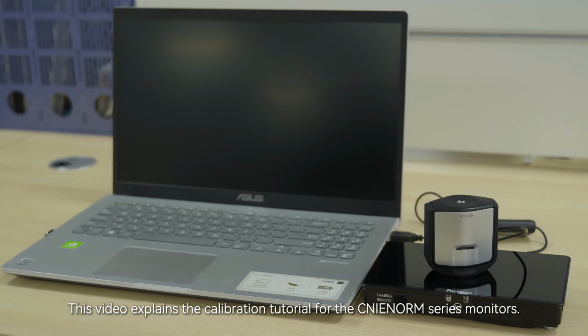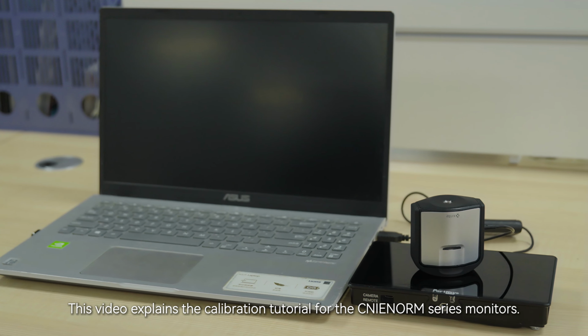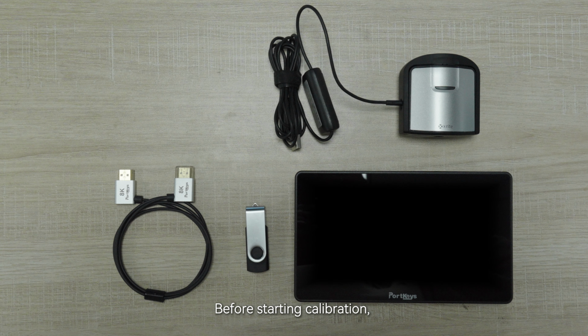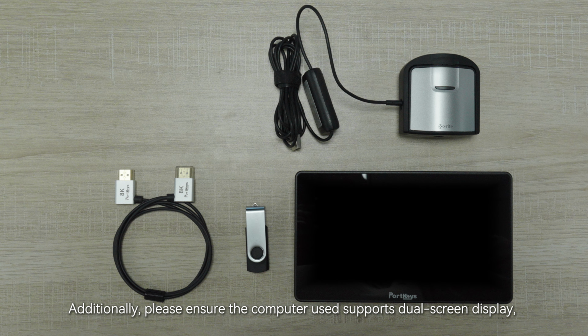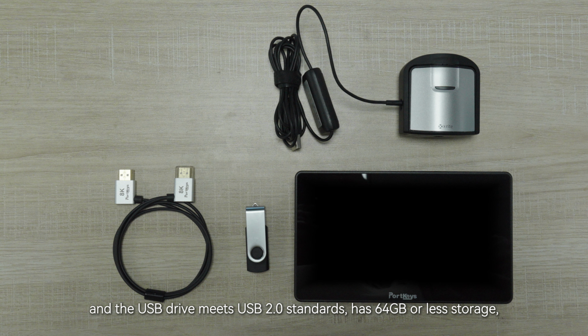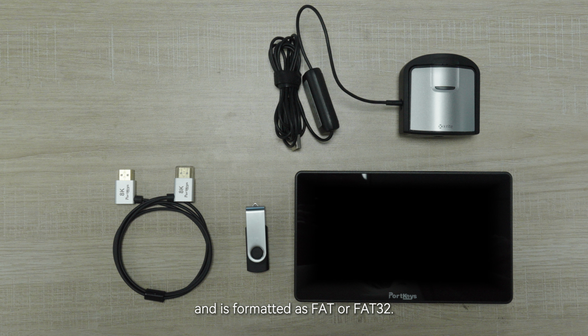This video explains the calibration tutorial for the CINENORM series monitors. Before starting calibration, please prepare a computer, a colorimeter, an HDMI cable, a USB drive, and the monitor that needs to be calibrated. Additionally, please ensure the computer used supports dual-screen display and the USB drive meets USB 2.0 standards, has 64 GB or less storage, and is formatted as FAT or FAT32.